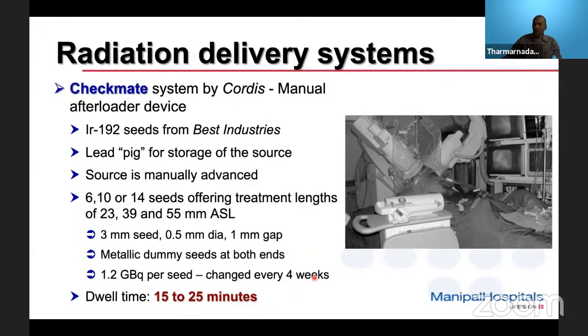We cannot do it like what we do in our HDR brachytherapy. Sometimes we go even up to 2 half-lives, but here it is not possible. The source has to be changed every 4 weeks, and even after that the dwell time will be of the order of 15 to 25 minutes. You remember in the beginning I told that iridium 192 we had to keep for a period of about 27 minutes.